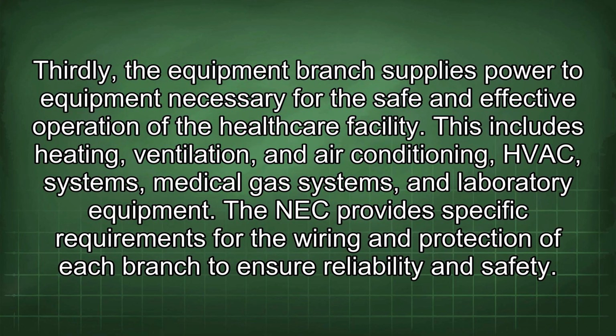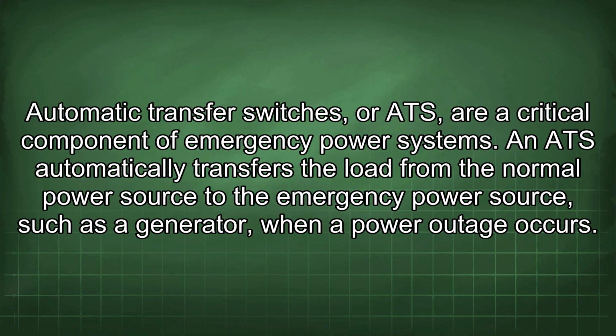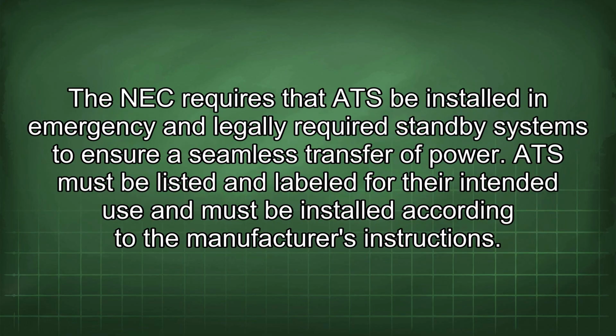Thirdly, the equipment branch supplies power to equipment necessary for the safe and effective operation of the healthcare facility. This includes heating, ventilation, and air conditioning, HVAC systems, medical gas systems, and laboratory equipment. The NEC provides specific requirements for the wiring and protection of each branch to ensure reliability and safety. Automatic transfer switches, or ATS, are a critical component of emergency power systems. An ATS automatically transfers the load from the normal power source to the emergency power source, such as a generator, when a power outage occurs. The NEC requires that ATS be installed in emergency and legally required standby systems to ensure a seamless transfer of power.